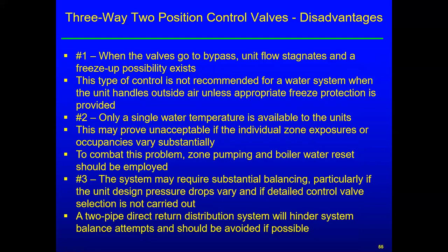Okay, some comments on three-way valves, two-position control. These are disadvantages. When the valves go to bypass, we stagnate the flow in the coil. And again, if we have any outside air available, we have freeze-up potential. And that covers the second bullet point as well. Number two, only a single water temperature is available to the units. If that's the case, then that's a disadvantage. But again, on a heating system, you could do boiler water reset. Chill water systems don't typically reset very much, maybe a little bit in really mild or dry weather, but not as much as the hot water systems do.